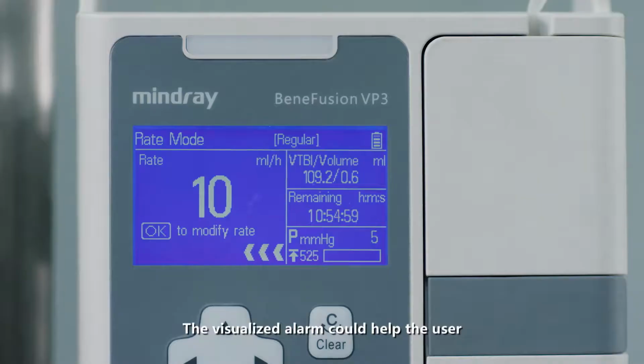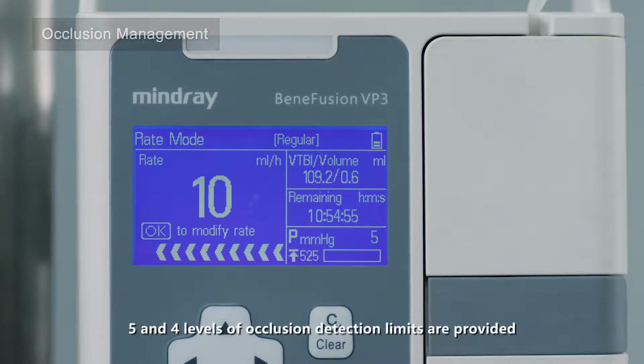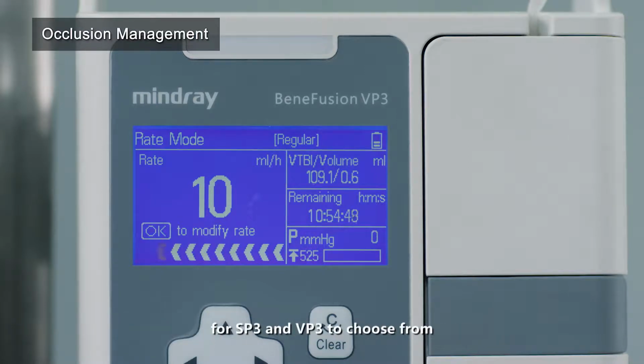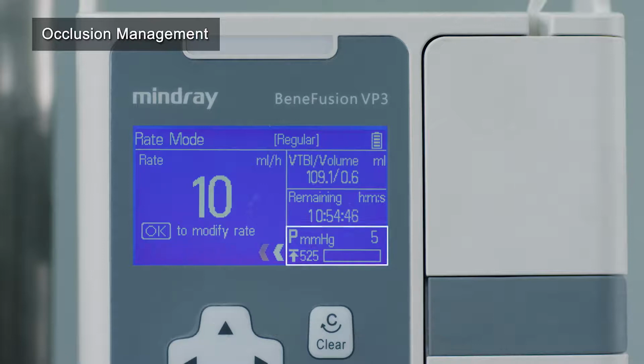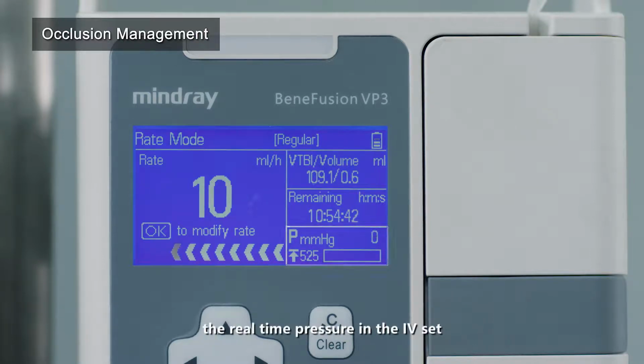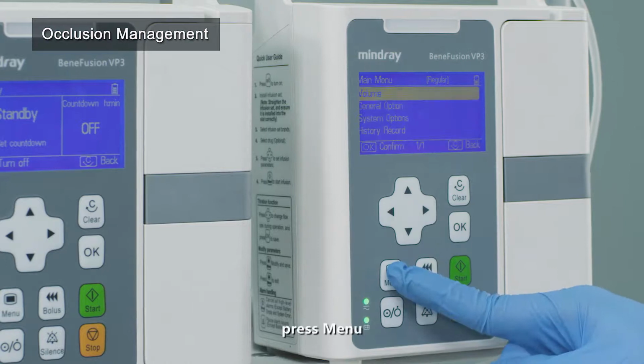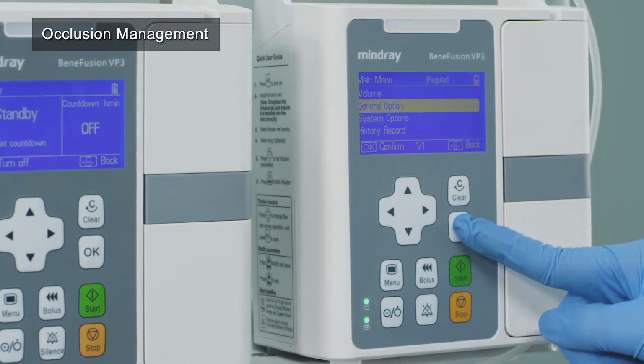The visualized alarm could help the user to fast locate the trouble. 5 and 4 levels of occlusion detection limits are provided for SP3 and VP3 to choose from. Dynamic pressure system indicates the real-time pressure in the IV set with the pressure number and the pressure progress bar. For adjusting the occlusion alarm limit, press Menu to adjust.